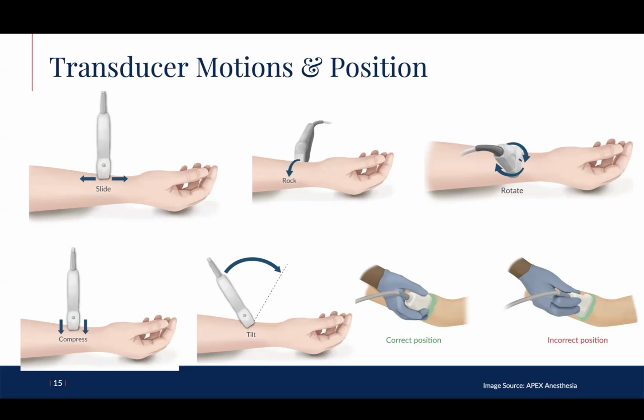Rotating motion in clockwise or counterclockwise directions are used when transitioning from short to long axis imaging and vice versa. The compressing motion can improve image resolution through reduction in distance between the transducer and target anatomy. The tilting motion changes the angle of incidence and assists with orienting the ultrasound beam perpendicular to the anatomical structure, which can improve the quality of the image.